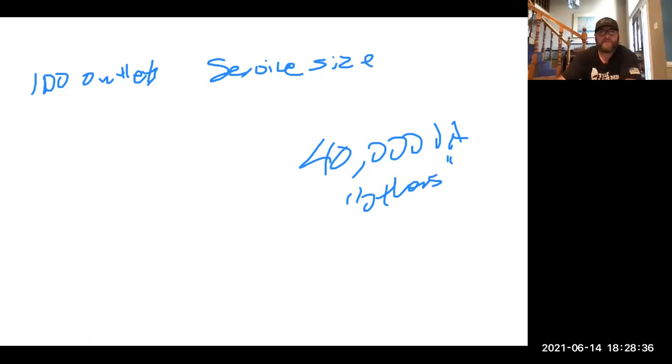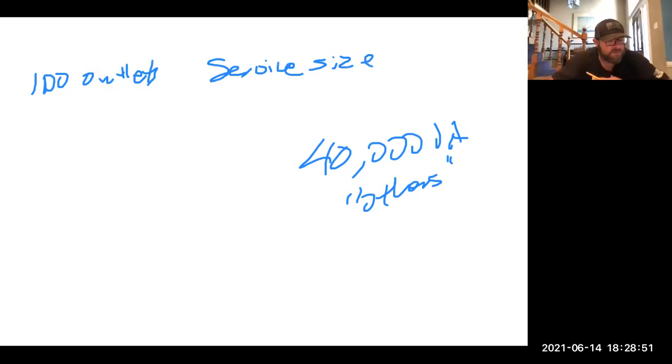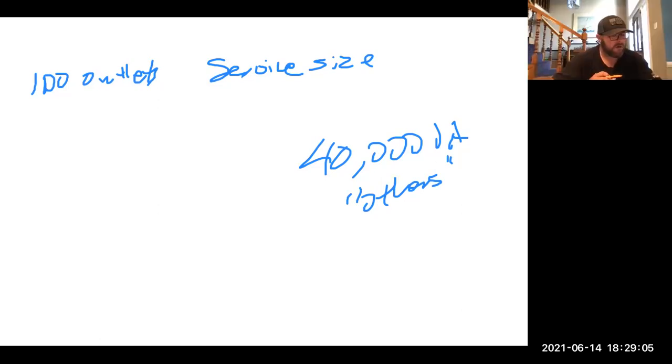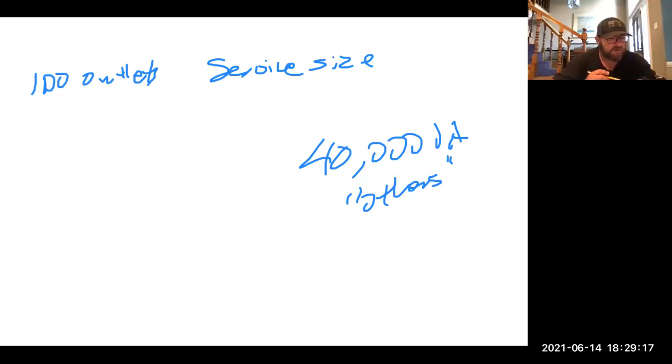Yeah. The only thing is, missing the square footage bothers me a little bit, because without that square footage, it's really hard to take a derate when you would normally. That's where I was looking, at 220.14 in office buildings. Receptacle outlets, except as covered in 220.14.